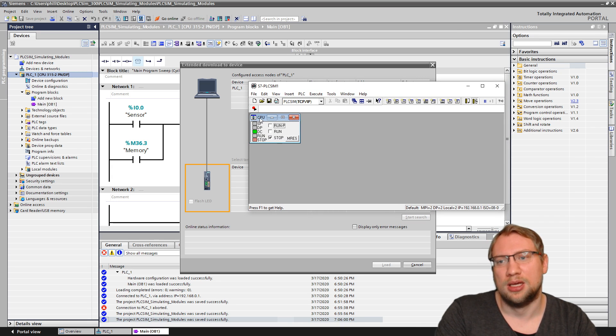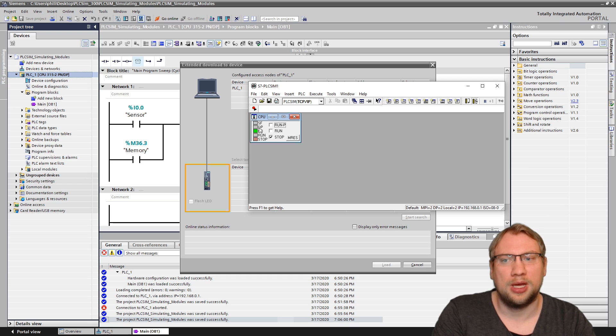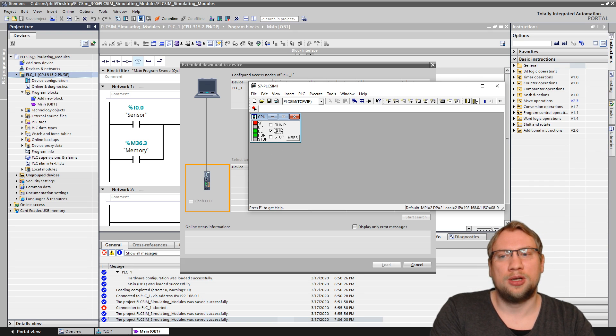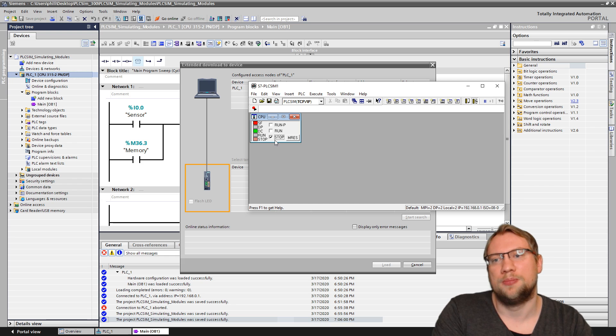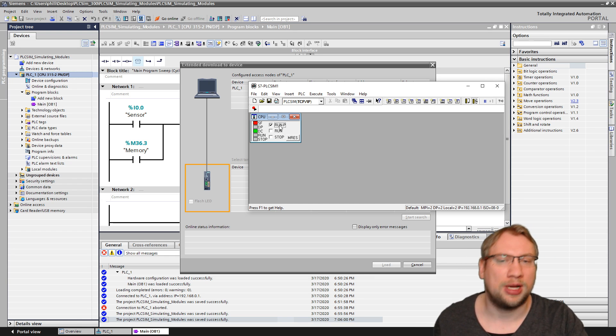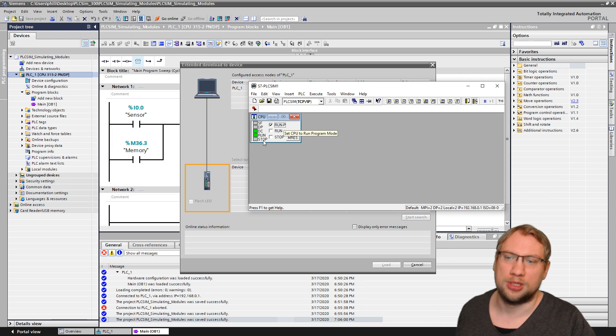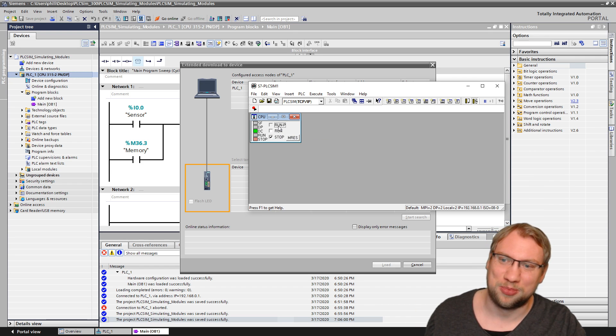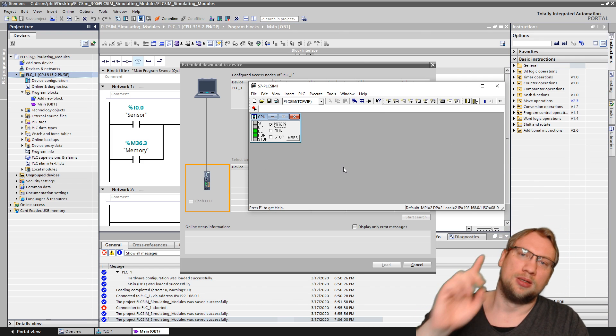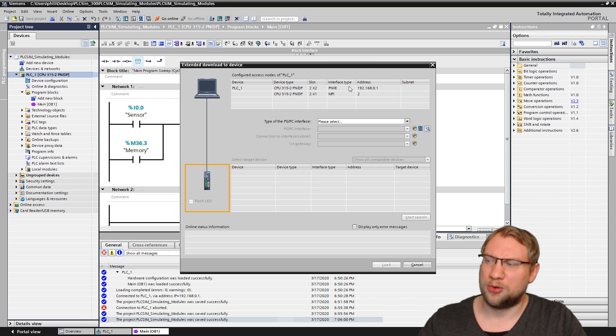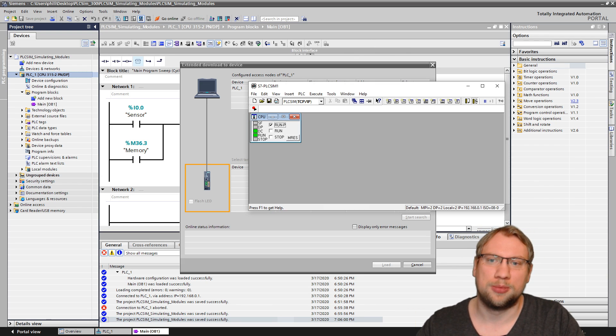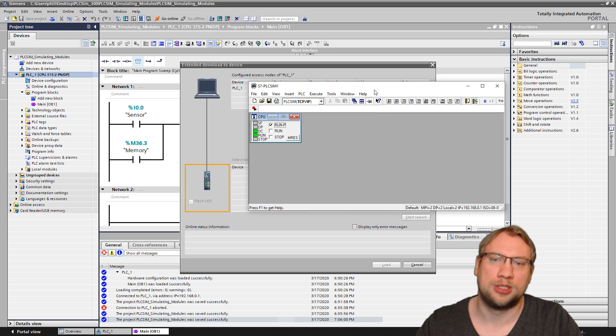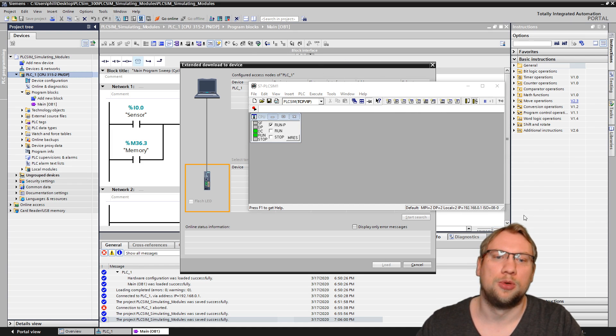A little window opens — this is our PLC. The thing that always opens first is the CPU, which has the common LEDs: SF, System Fault, DP, DC, Run, Stop — all the LEDs we know — and also a switch that selects between operating modes. I usually leave this switch on Run P, which means it runs the program and you can still download to it. If you set it to just Run you cannot download programs anymore. If it's in Stop you can download but the PLC won't execute the program. So Run P is my preferred setting. One very important thing: if I click into TIA Portal the simulation window goes to the background, which is inconvenient. There's a little pin button — I pin it and now it's always on top, even when TIA Portal is active.